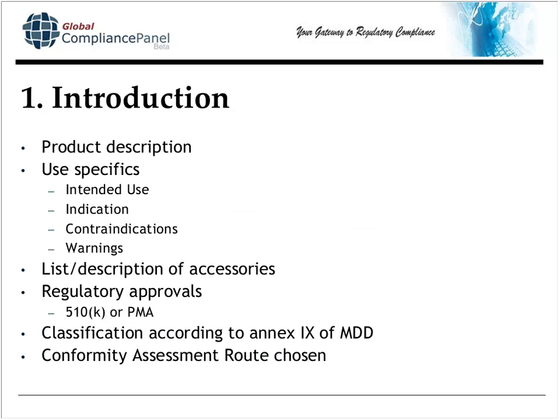The technical file introduction begins with a product description and use specifics. Quite a bit of this was not actually required in your design history file. Contraindications and warnings, for example, are required in a technical file but were not explicitly required in your DHF. A list or description of each of the accessories is also required, along with what regulatory approvals you have, and per Annex 9 of the Medical Device Directive, what classification your device is. Classification according to the Medical Device Directive is completely different from classification in the U.S.